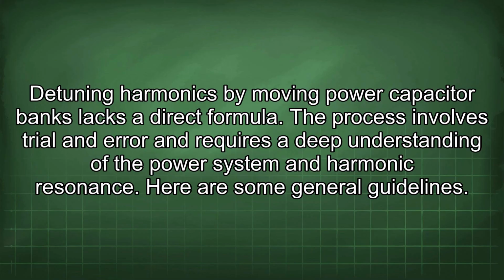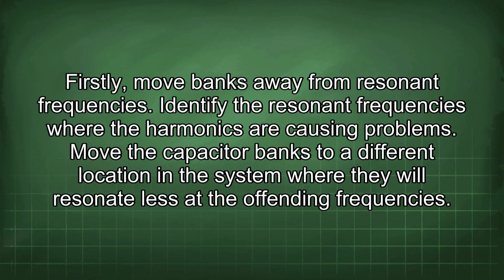Detuning harmonics by moving power capacitor banks lacks a direct formula. The process involves trial and error and requires a deep understanding of the power system and harmonic resonance. Here are some general guidelines. Firstly, move banks away from resonant frequencies. Identify the resonant frequencies where the harmonics are causing problems. Move the capacitor banks to a different location in this system where they will resonate less at the offending frequencies.